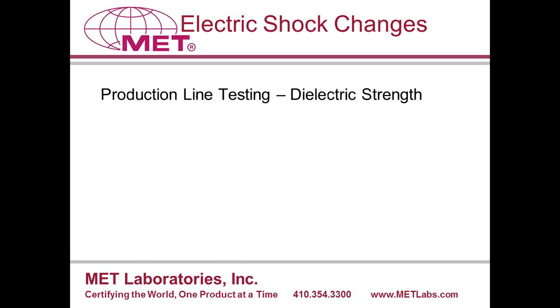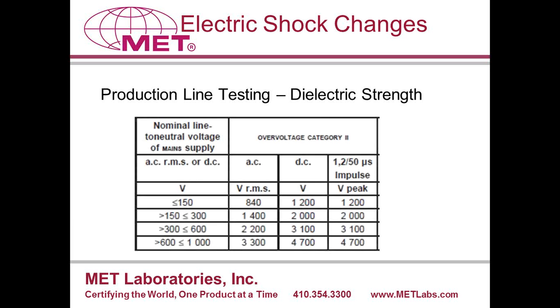Now, luckily for routine testing, the values for dielectric strength testing are primarily the same. For 120-volt products, the values are identical. For 220 to 240-volt products, the numbers have been rounded up slightly from 1390 to 1400 VAC and from 1970 to 2000 VDC. The ramp time for AC and DC testing has been expanded to 5 seconds, which is less severe. The duration is still 2 seconds.